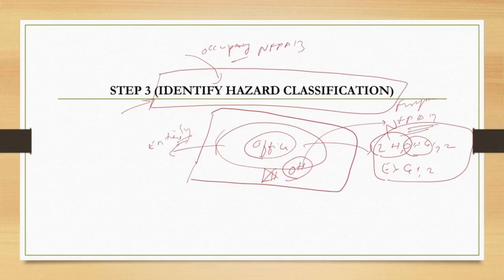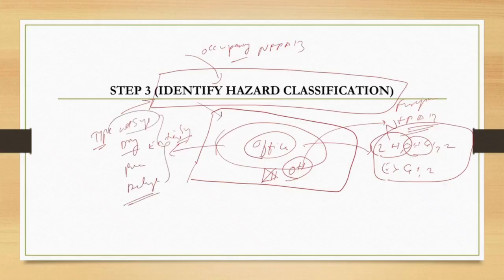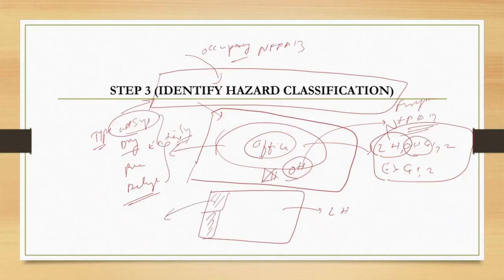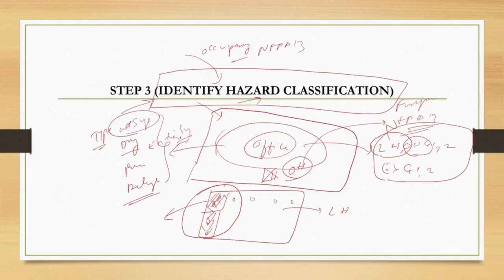We also need to decide what type of system we are using: wet system, dry system, pre-action system, or deluge system. In our case we consider a wet pipe sprinkler system. If an office building comes under light hazard but there are a couple of rooms classified under a different hazard, those rooms' sprinklers need to be spaced according to that particular room's hazard classification.